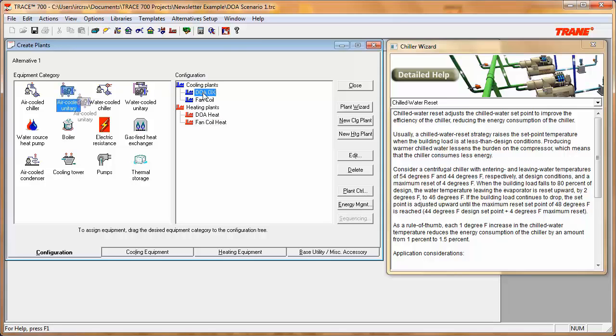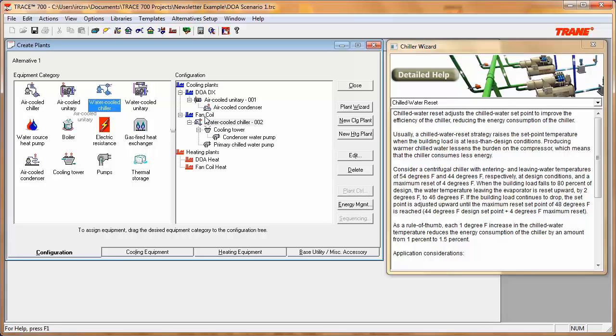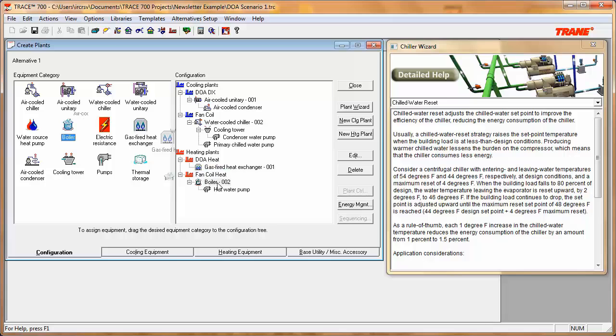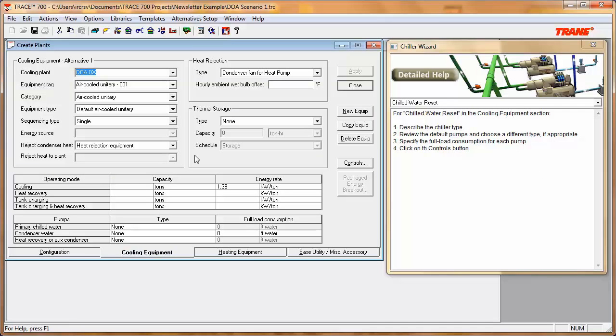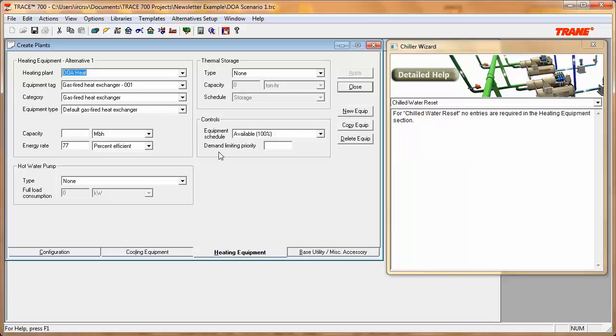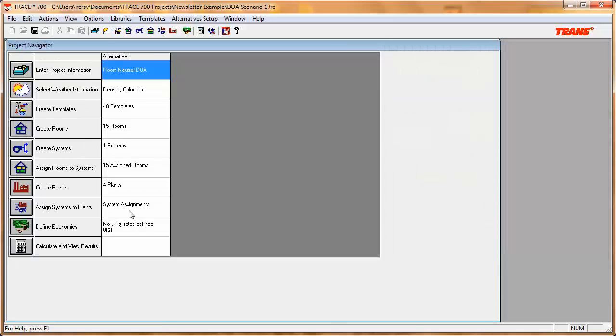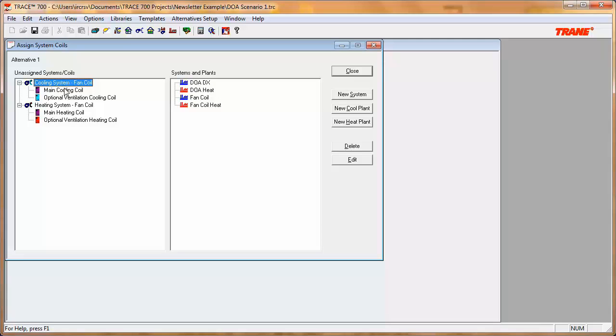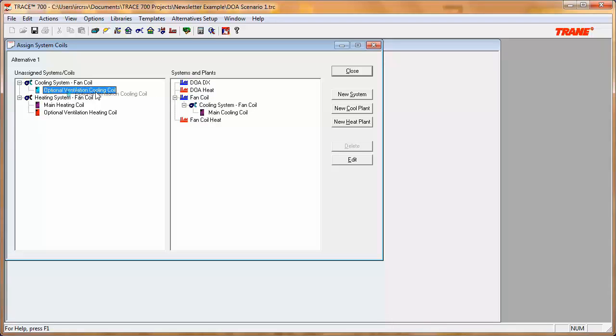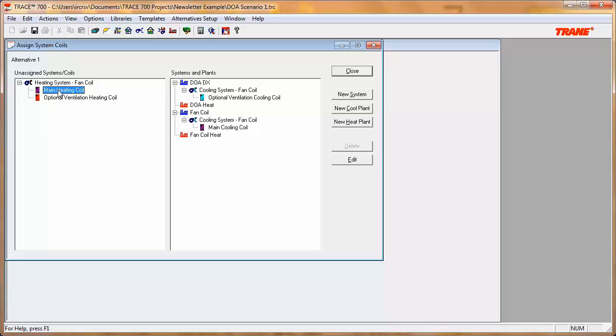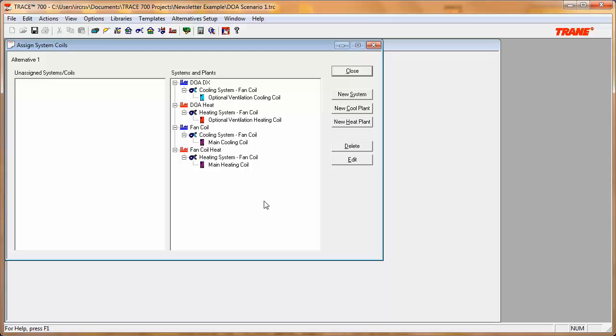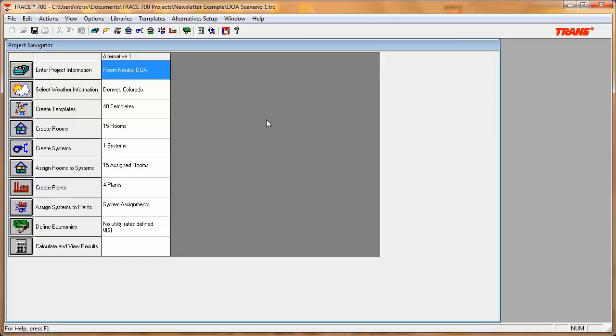I'll drag the cooling equipment onto the DOA chiller and onto the fan coil plant, and then for heating, a gas-fired heat exchanger for the DOA and a boiler for the fan coil heat. In the cooling and heating equipment sections, I'll leave those as default. In Assign Systems to Plants, we can split the main cooling coil — which is the fan coil — from the DOA cooling coil. I'll drag the main cooling coil onto the fan coil plant and the optional ventilation cooling coil onto the DOA DX plant, and do the same with the heating coils. Now the DOA is configured as a separate plant from the fan coil. That's how we model our first scenario.